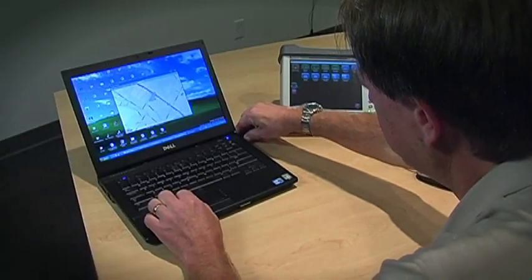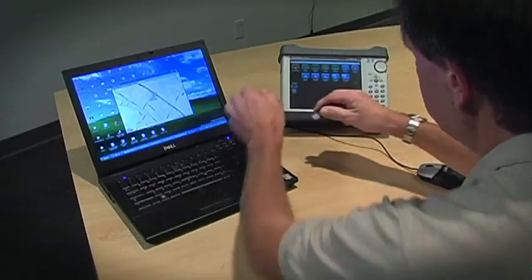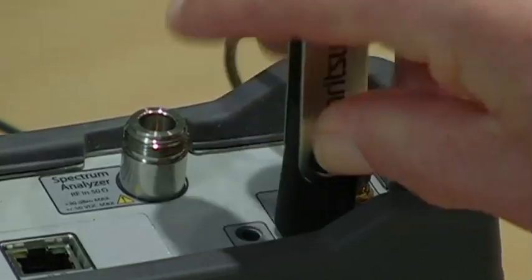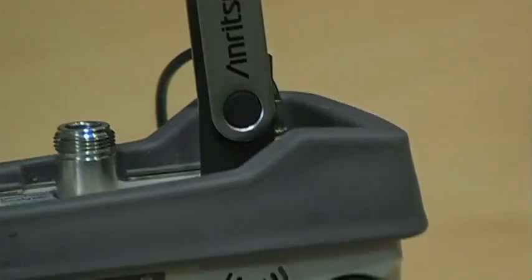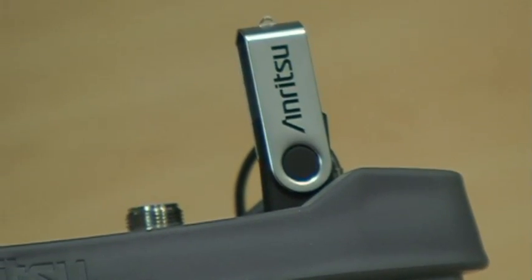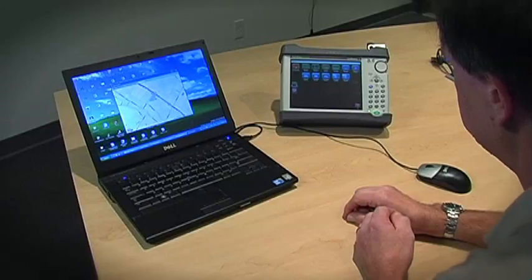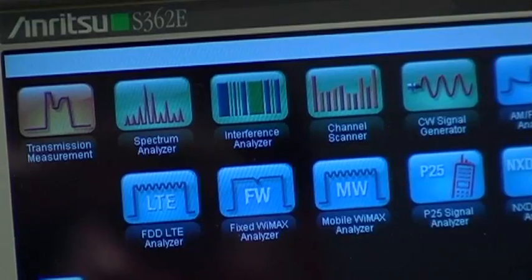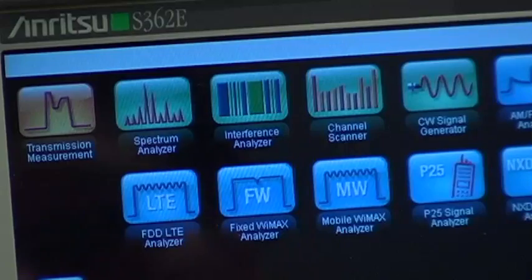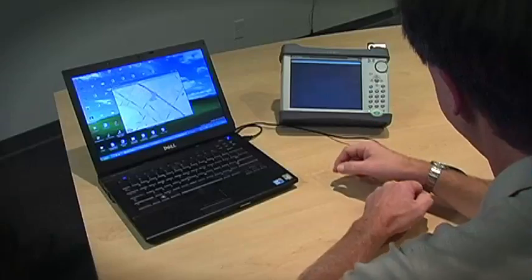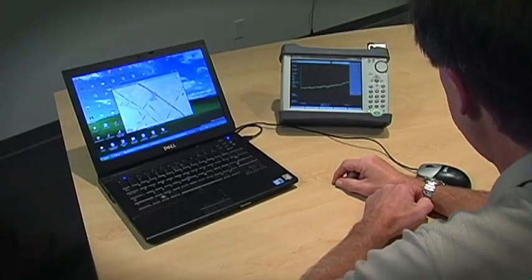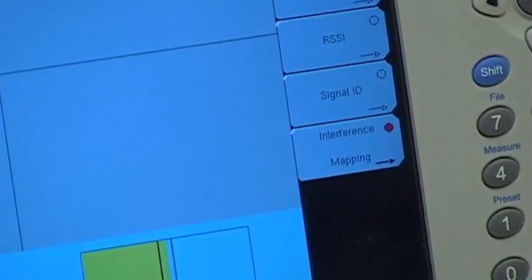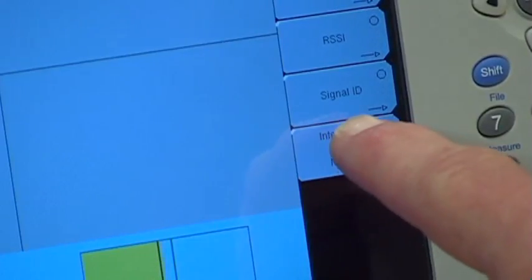You can then insert the USB into the instrument's USB port. The instrument has many different mode capabilities, but for interference location mapping, you have to be in the interference analyzer mode. One way to enter this mode is by accessing the main menu, pressing the interference analyzer icon, and pressing the interference mapping soft key to highlight the selection, then touching the key again to enter the menu.